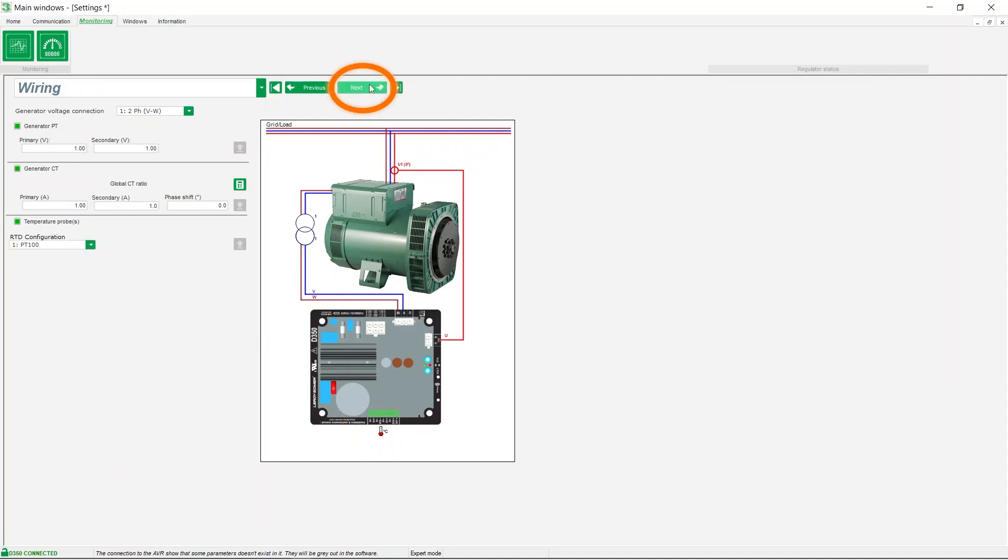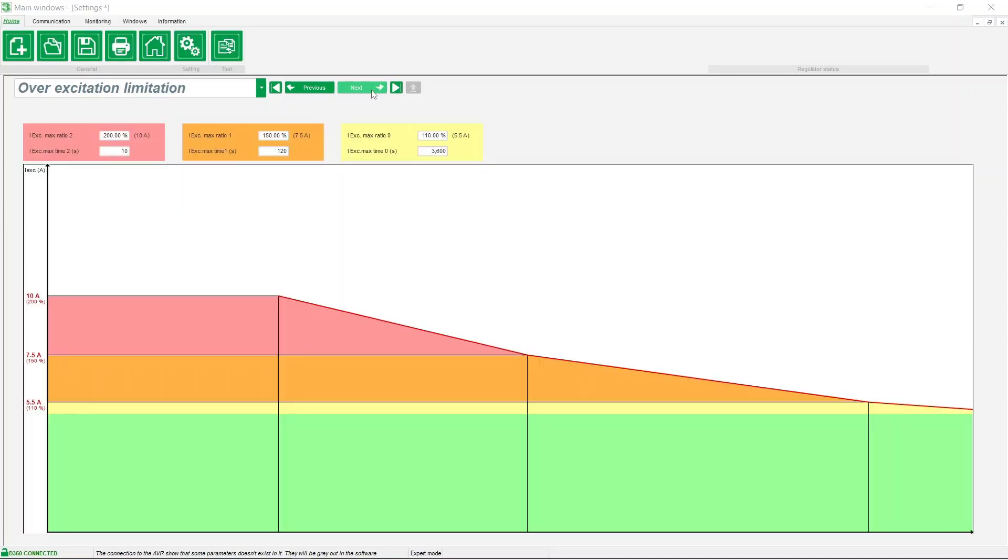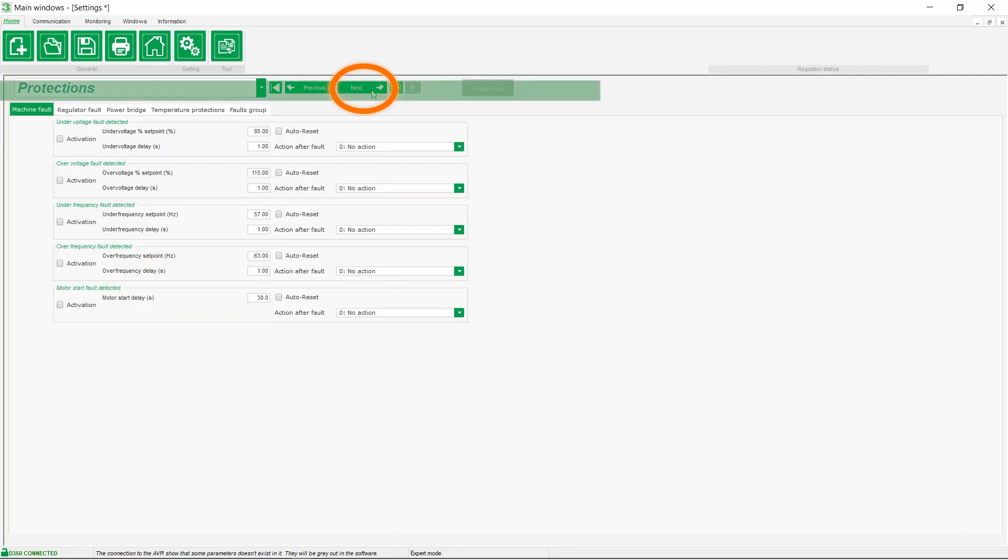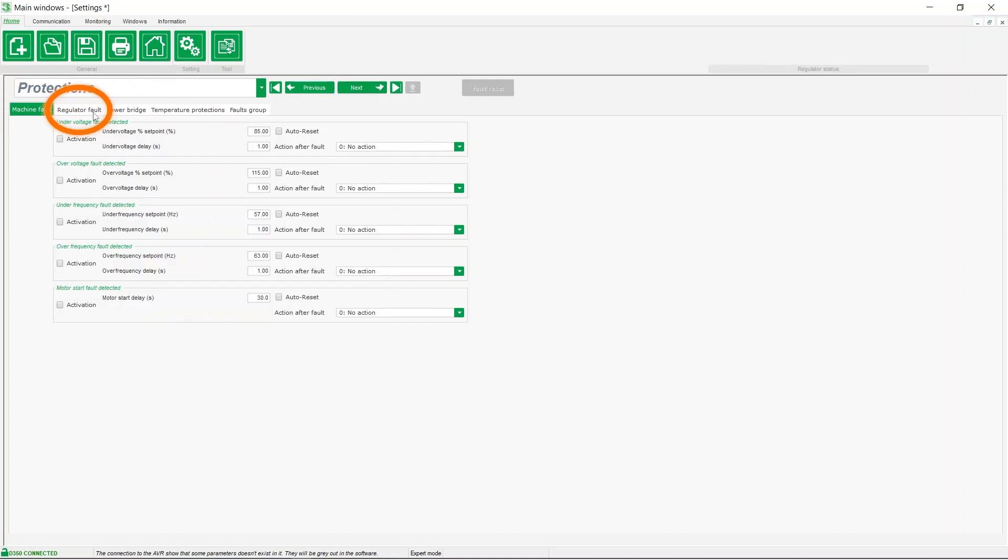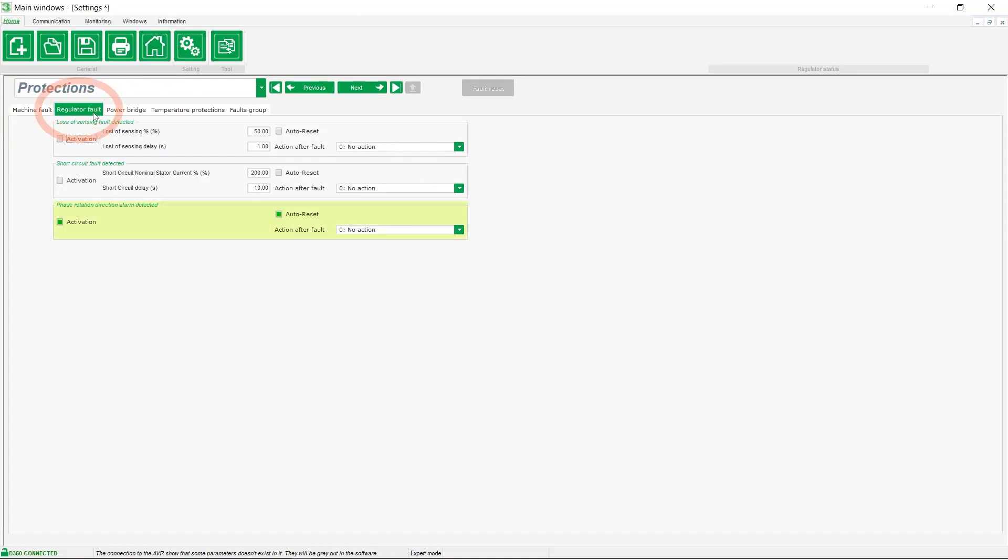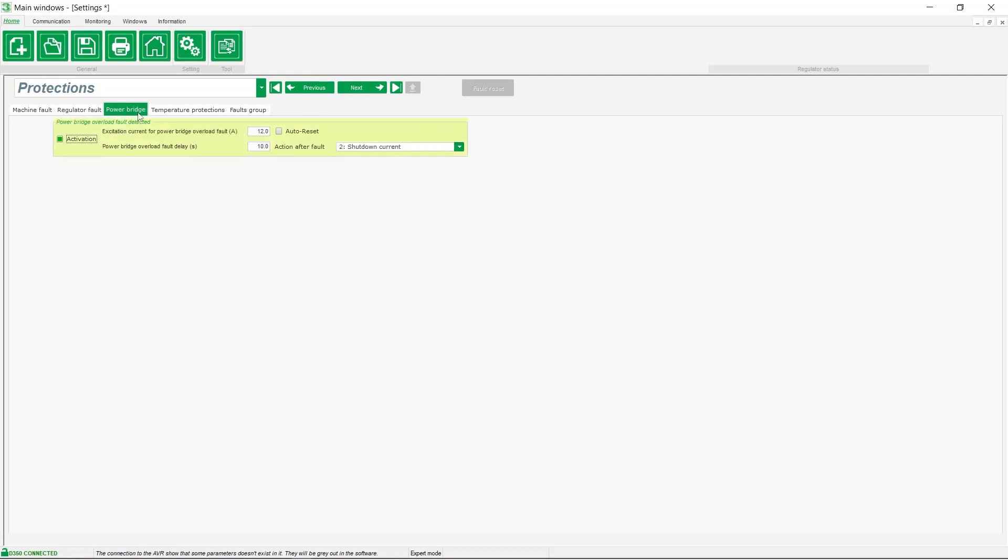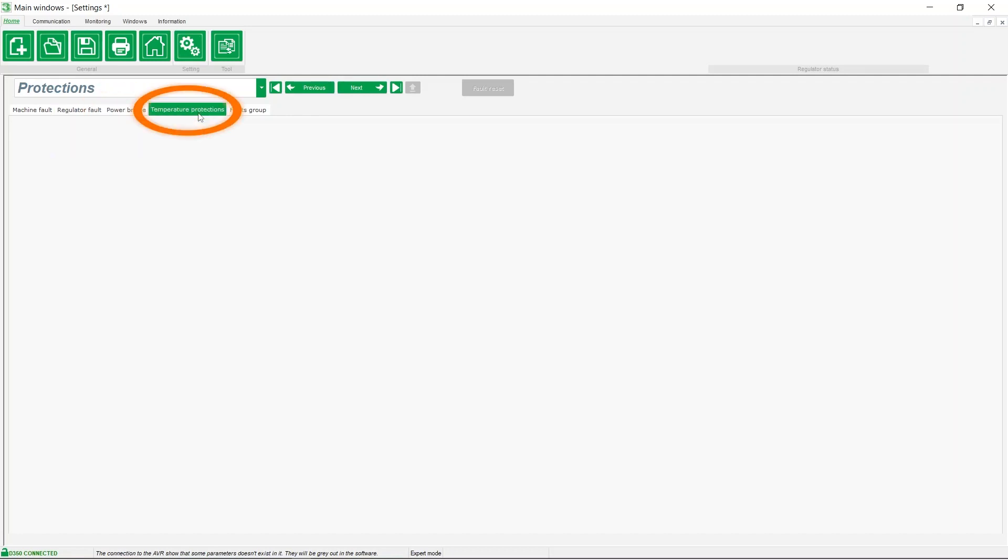Click on next. The values for over-excitation limitation are automatically filled and typically do not need to be modified in a standard application. Now let's look at the machine protections. We can protect the alternator against machine faults such as under-voltage fault, regulator faults such as loss of sensing power bridge faults. The temperature protection option is accessible once a sensor has been selected in the wiring section.